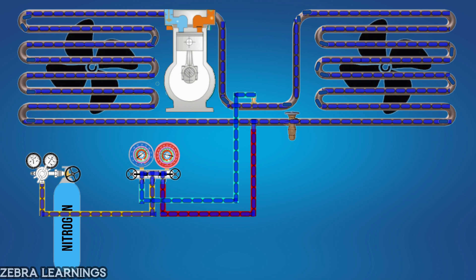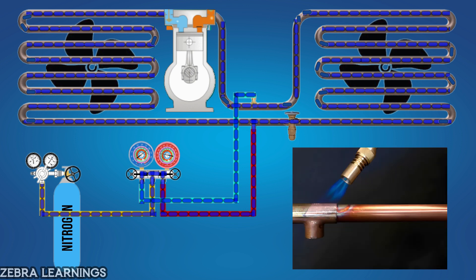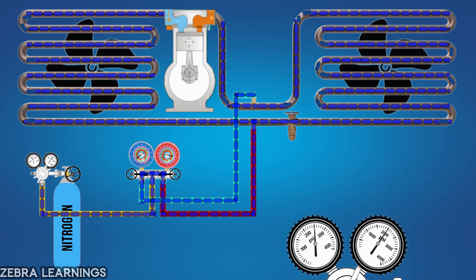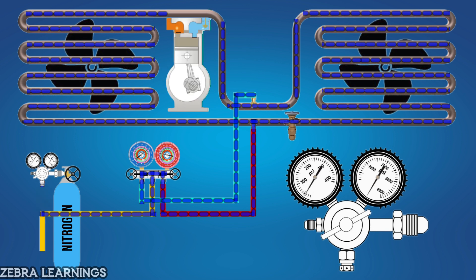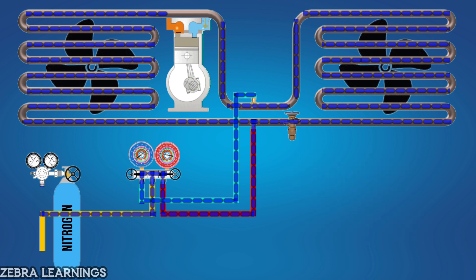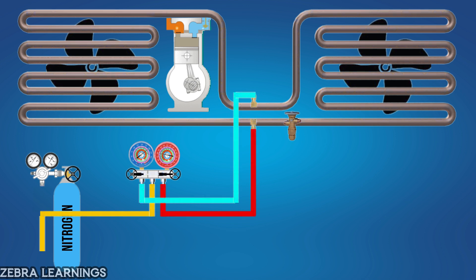We will discuss in the next video how to repair a detected leak using the brazing method. If there are no leaks, close the nitrogen cylinder and turn the handle on the regulator fully counterclockwise to reduce the pressure. Then remove the yellow hose from the regulator and slowly open the valve on the low-pressure line to release all the nitrogen gas. Next, vacuum the unit, recharge it with refrigerant, and run it.